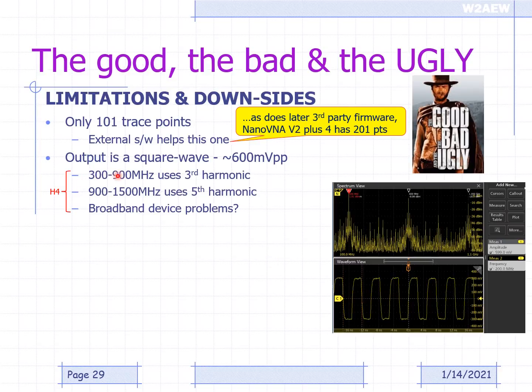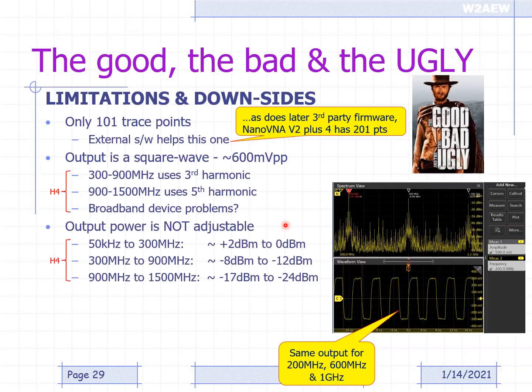Above 300 meg up to 900 meg, the VNA uses the third harmonic to make all the measurements, and then above 900 up to 1.5 gig, it uses the fifth harmonic. So this 200 megahertz square wave shown right here is the same output that you get if you were measuring at 600 meg. It's the same output that you get at 1 gig. We just are using a different frequency range in making the measurement. So you have to think about whether that is going to affect what you're measuring. Is the device I'm measuring going to care that it's getting hit with a square wave that has this harmonic energy or not? So you have to think a little bit about that.